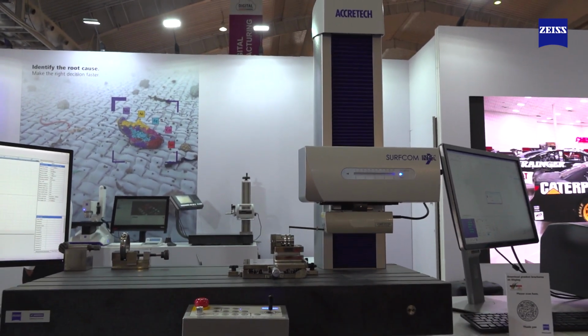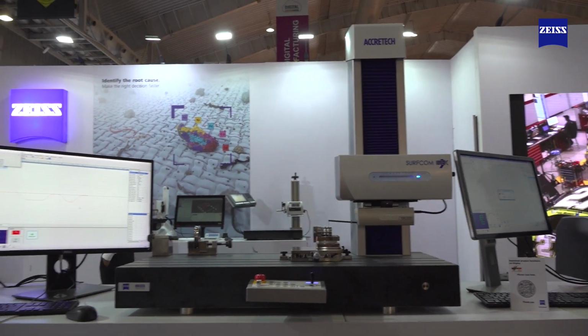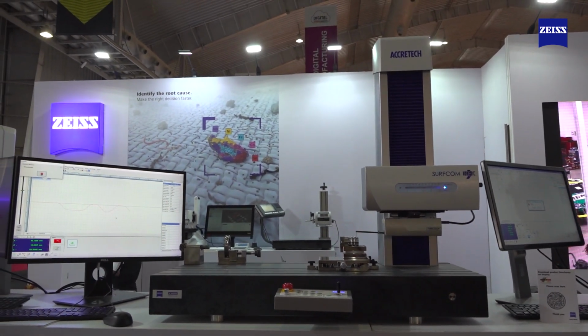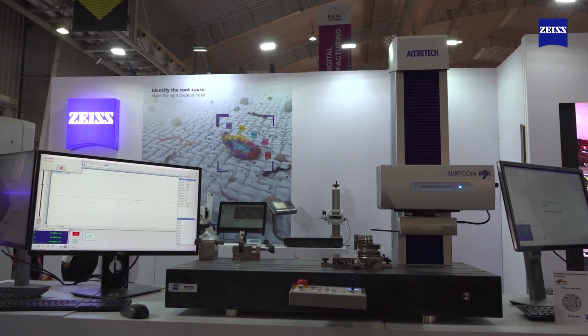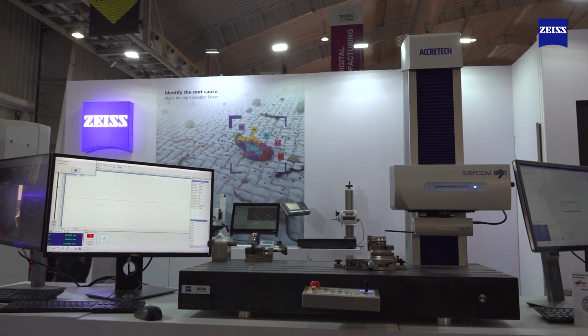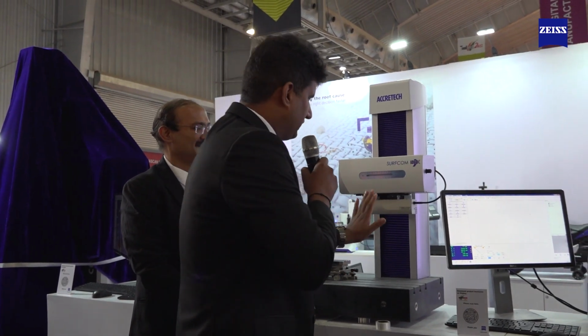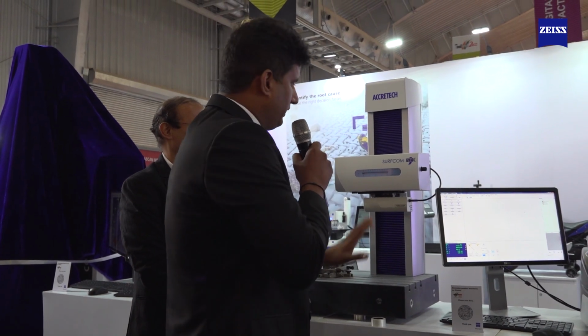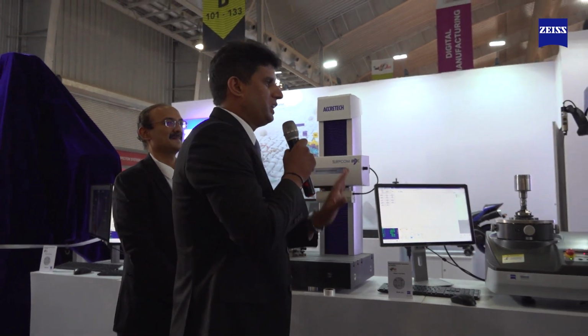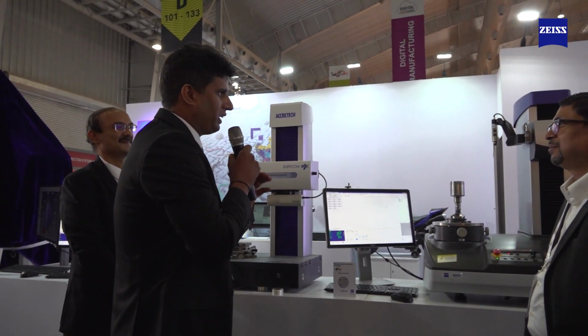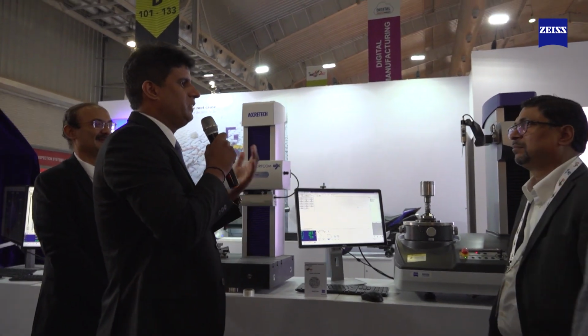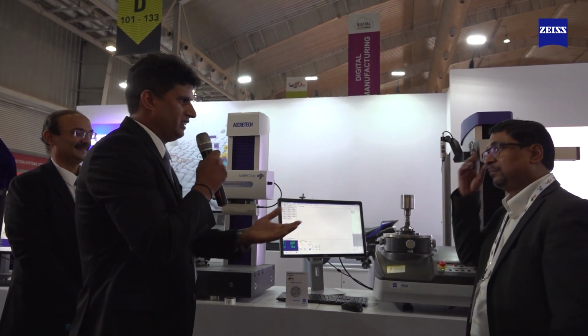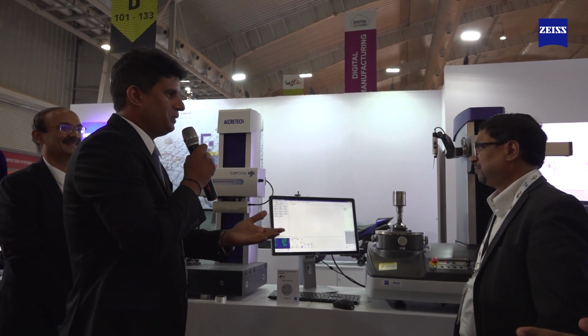The most important thing is the sensor we use here is called a hybrid sensor, which can measure both roughness and contour in a single pass, and we don't have to change the stylus. This machine is mainly designed for the bearing industry, which could be related to IC engines, EV, or even aerospace. The bearing is a very common part we use.